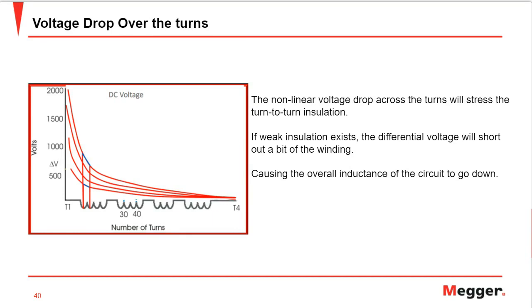So we create an impulse of voltage in the windings and the voltage decays, right? As we can see on the graph, there's a high voltage at the initial and then it eventually decays. So the non-linearity of the voltage drop, as shown in the figure, appears during the spike of the VFD switching, or the contact bouncing. So the first few turns experience the majority of that voltage.